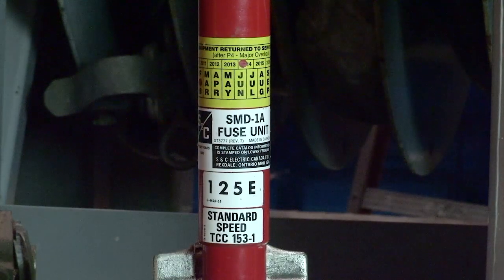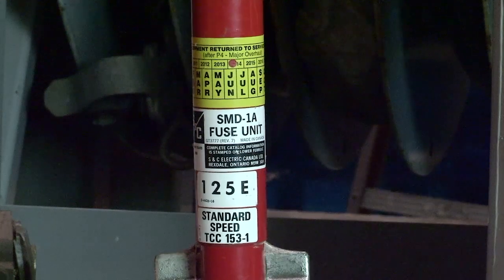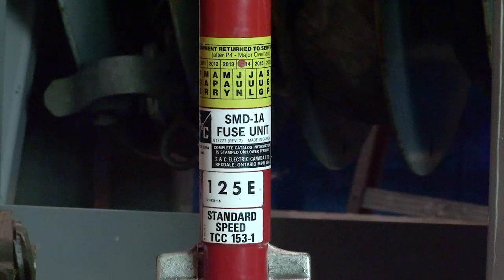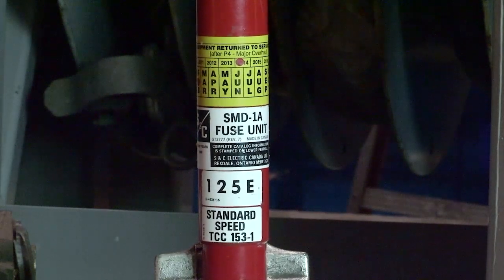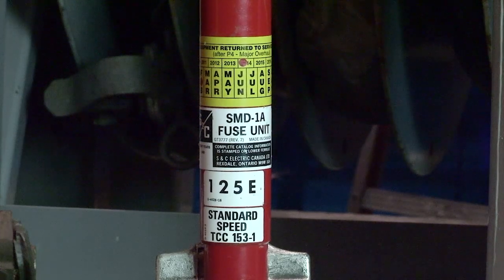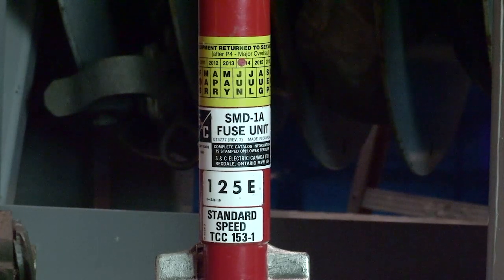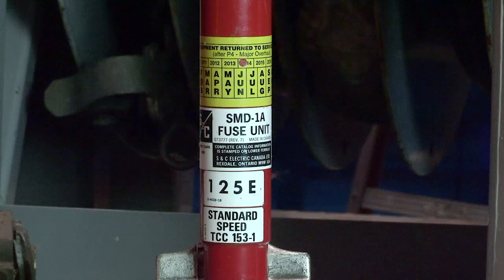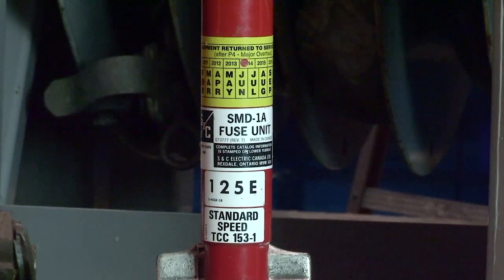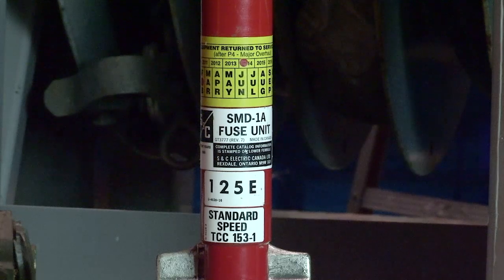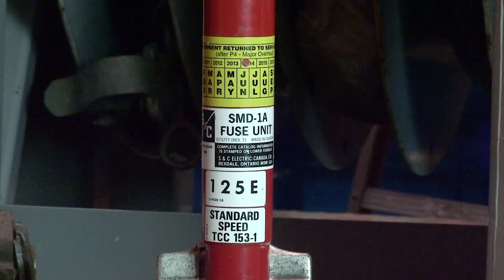So this here is an SMD standard 1A type fuse. This is a 125 amp rating. And down there at the very bottom where you see a standard speed TCC 153. That TCC is the time characteristic curve that I was showing you in the diagrams earlier, showing what type of curve this fuse will have on our system.